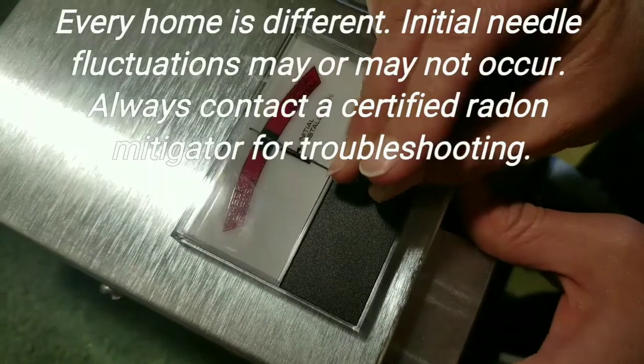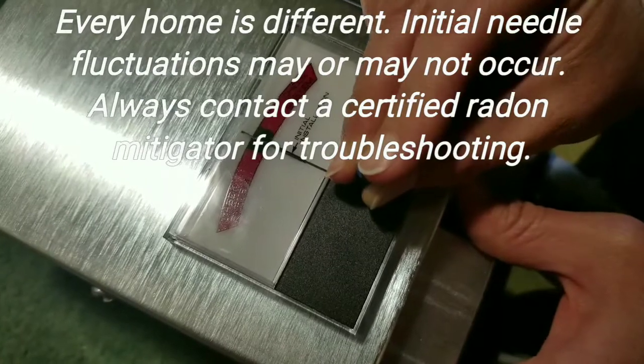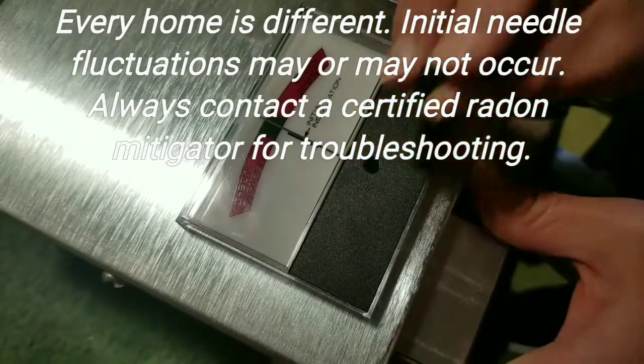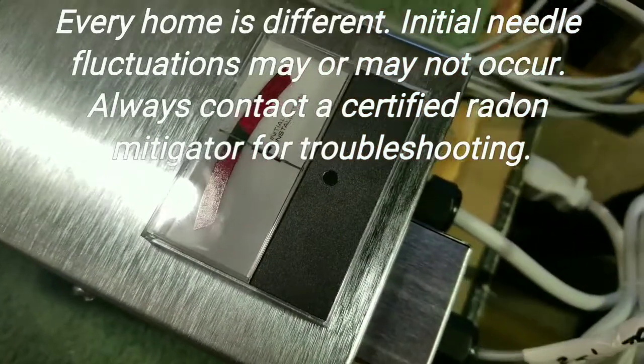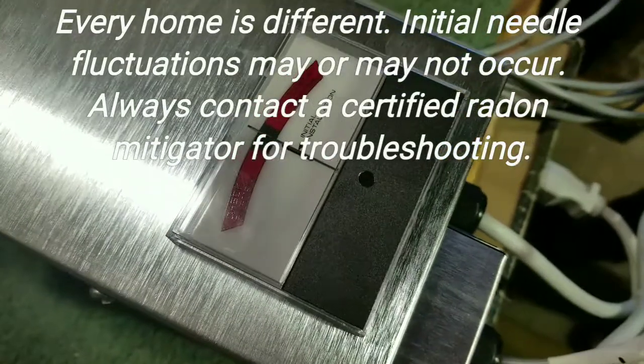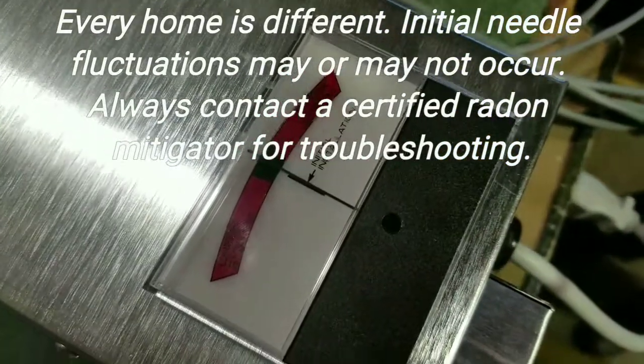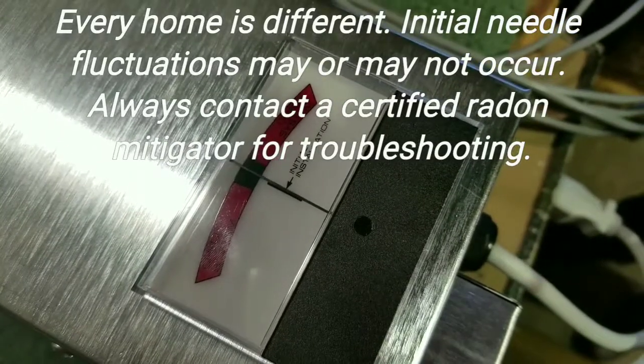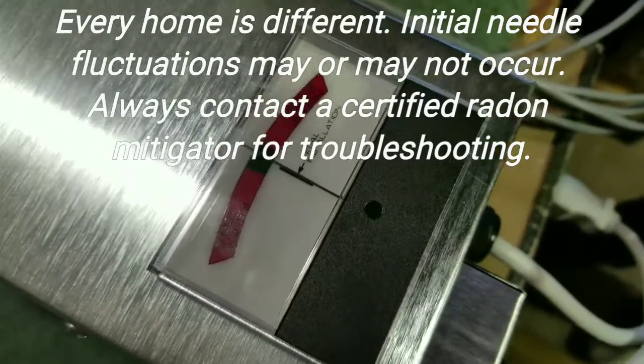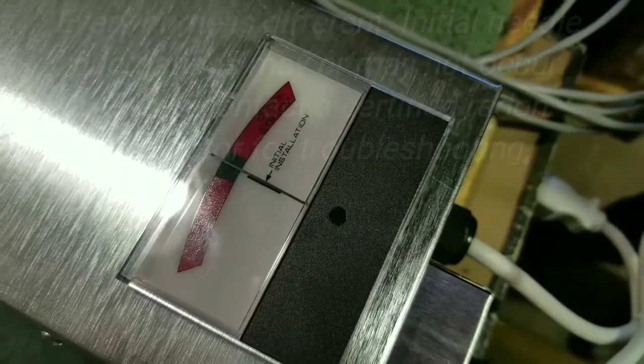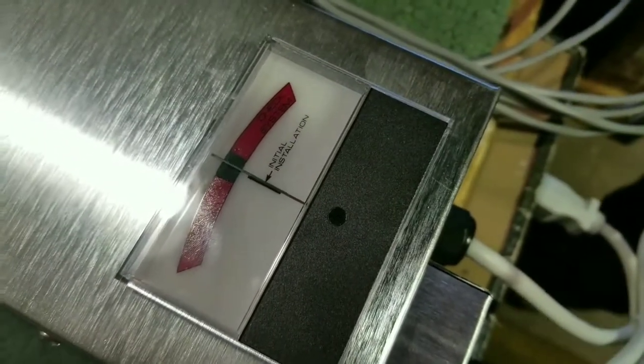Typically you'll want to do this centering a day or two after the system has been installed because issues with the system such as moisture in the soil and other factors can have that needle move over time. And once you adjust that needle, you do not want to need to adjust it again without doing a radon test. So wait about two or three days before you do that initial adjustment so that the soil can dry out.